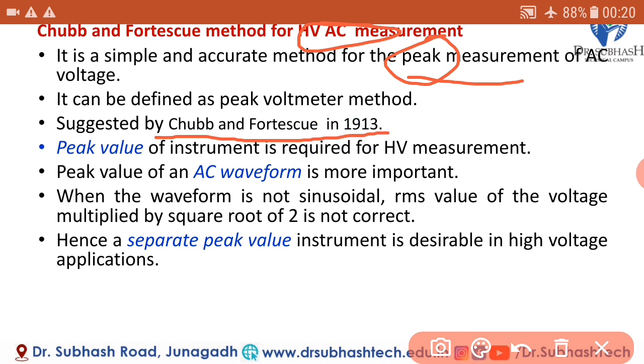Peak value of the instrument is required for high voltage measurement. Peak value of an AC waveform is more important. When the waveform is not sinusoidal, the RMS value of the voltage multiplied by square root of 2 is not correct. See, generally we find the peak value by using a formula. Peak value is equal to root 2 into RMS value, but it is only applicable for a pure sine wave. If the waveform is not sinusoidal, then this method is incorrect. So hence a separate peak value instrument is desirable in high voltage applications.